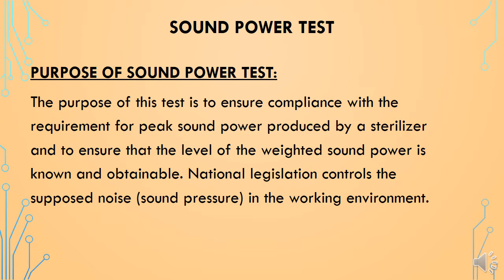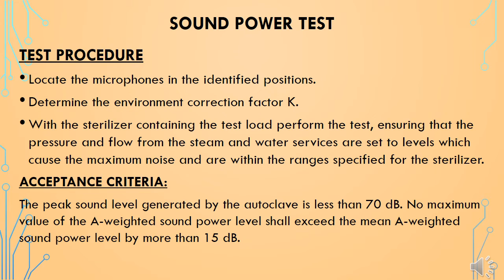The next qualification test is the sound power test. Its purpose is to ensure compliance with the requirement of peak sound power produced by the sterilizer and to ensure that the level of weighted sound power is known. National legislation controls the noise or sound pressure in the working environment. To perform the test, locate microphones in the identified locations, determine the environment correction factor K, and with the sterilizer containing the test load, perform the test ensuring that pressure and flow from steam and water services are set to levels causing maximum noise within the specified range.